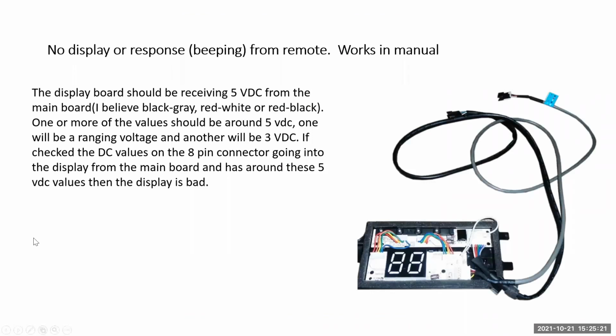So on your display boards, and I just mentioned the 88 code, as you can see here on this picture, if the display is malfunctioning and it's not an 88 code, it just lights everything up, and like most digital displays, it lights them all up and looks like an 88. So on the display board, you should be receiving 5 volts DC from the main board. And you can check that at the gray and black wire, and then the red and white wire, and then the red and black wire. One or more of these values should be around 5 volts DC.